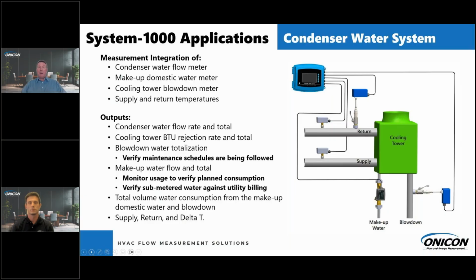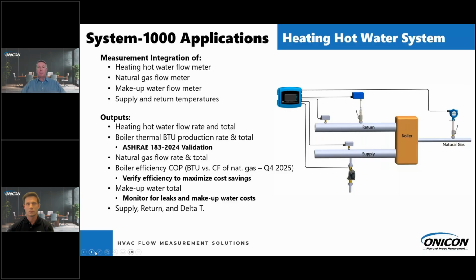And if you live in a locale where they do sub-metering for cooling towers, it allows you to verify your sub-meter water usage against your utility billing to make sure you're getting that full credit as you planned. So this type of install will give you your total volume of water consumption from the makeup, the domestic water, and the blowdown. And of course, you get your data of supply, return, and delta T back out of your BMS. Now let's look at a heating hot water system.